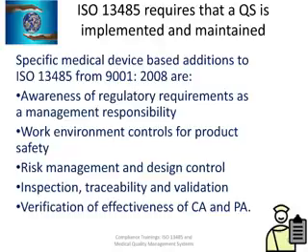Okay? And ISO 13485 requires that a quality system is implemented and maintained. Say you're a small company starting up, an inventor starting up a small company. So you have to register yourself for 13485 if you want to sell your products, and get it audited for 13485. And what does it require? It requires that you implement a quality system, okay?